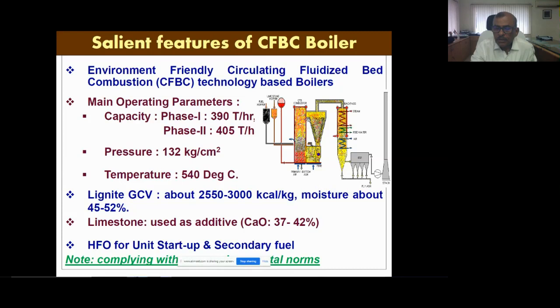And you can see in the photographs, this is the main combustor area. This is the cyclone, which is completely refractory lined. These are the fluidized bed heat exchangers. I am saying this because this terminology will be used. Then this is the main back pass, where all the superheater, reheater and steam circuit will be. Then the economizer, then the air heater, and then it goes to the ESP and to the chimney.